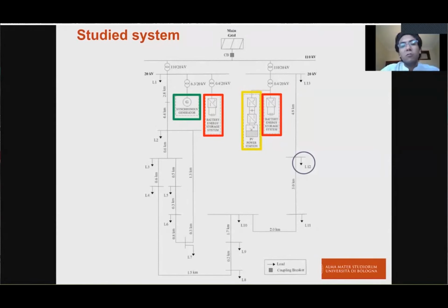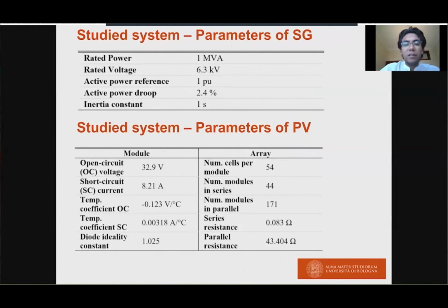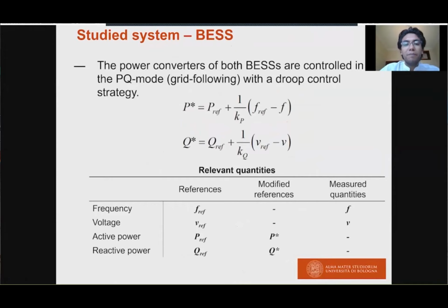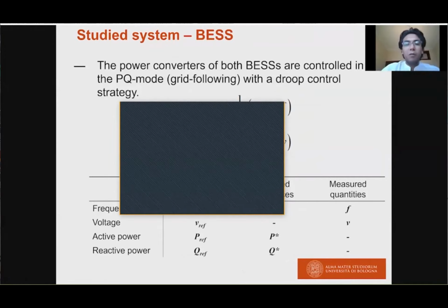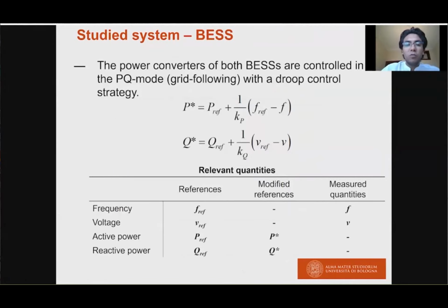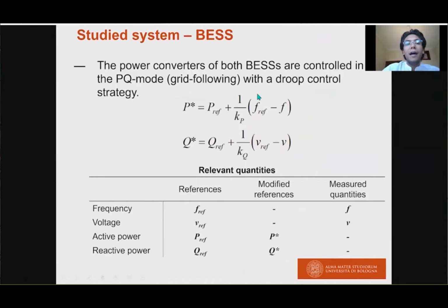Here we reported the parameters of the synchronous generator and the PV power plant. And here we describe the battery. Both batteries are controlled in the grid following mode with a droop control strategy in which the active power responds to changes in the frequency and the reactive power responds to changes in the voltage.